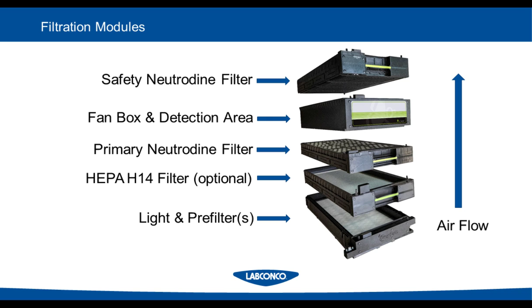And then lastly, sitting on the very top of this is that safety filter. So after the fan and the detection area, that's also where the sensors are located, we place a redundant, fully redundant safety filter on top. Once we detect molecular breakthrough of the primary filter, and we sound that alarm down to the user, we also have that secondary safety filter sitting on top to capture whatever molecules did break through and still return clean air back into that laboratory. Very important differentiation with the DH3 technology.